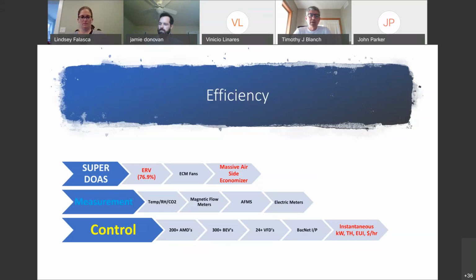And then the third little arrow there is that we found out with the DOAS, the super DOAS, we created a massive airside economizer, and that is significant in the energy efficiency of the building. It allowed us to turn off the chiller plant 7 months out of the first year that we operated it. We did not expect that great of a benefit, but when you can bring in an almost unlimited amount of outdoor air, you can operate with your plant off many, many hours because it doesn't really matter what your cooling load is. You can bring enough air in to handle it. So that was kind of a surprise at the amount of benefit we got from that airside economizer.